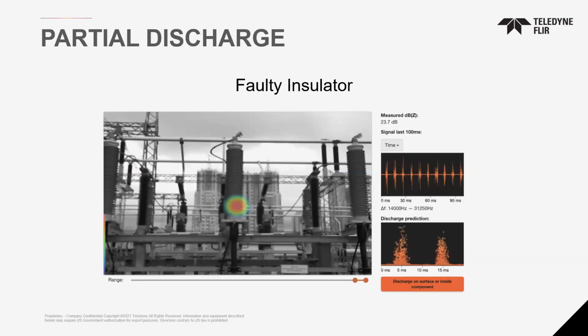So here is an image of a faulty insulator. As you're walking through your substation, you might want to take images of anything that you see, like this insulator, where we're getting this rainbow indicating partial discharge. So you stop and you take the image, you save it to the cloud, like we said, and then you also want to do just good practice. You also want to perform a visual inspection. Maybe you have binoculars on you if it's far away, but you want to make sure that the insulator is clean of any potential dirt, debris, bird droppings that could cause discharge on the surface of the device, right?